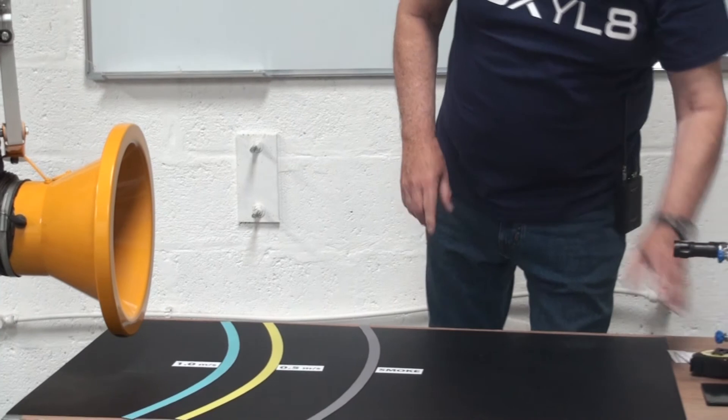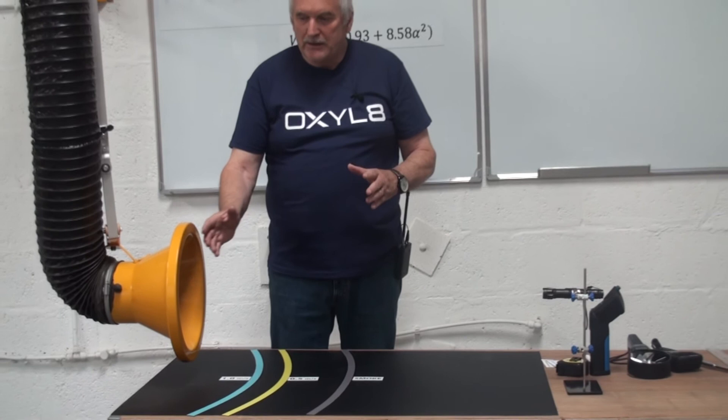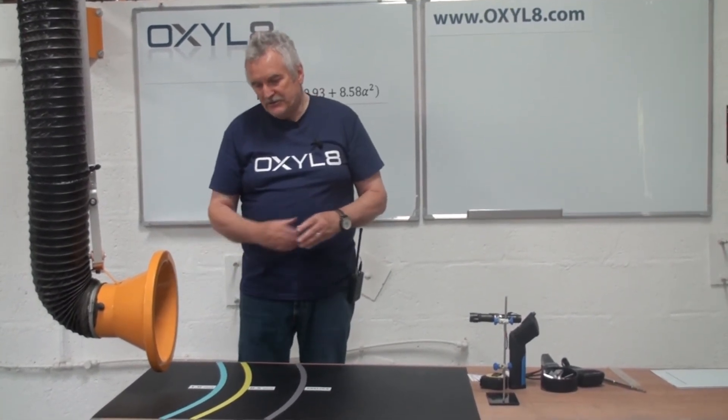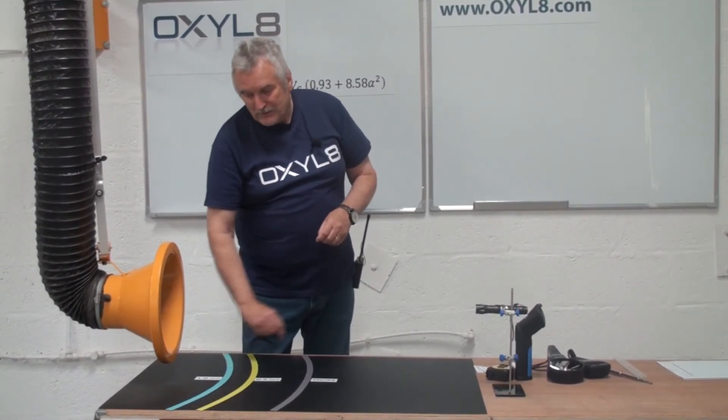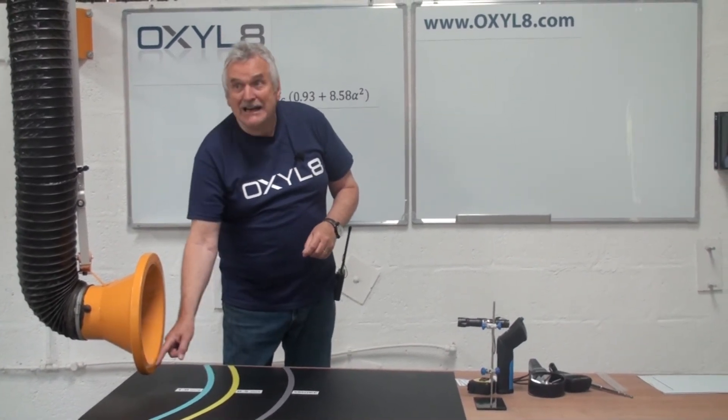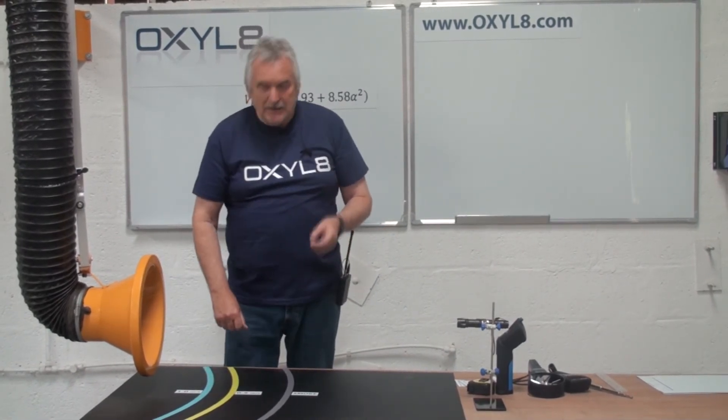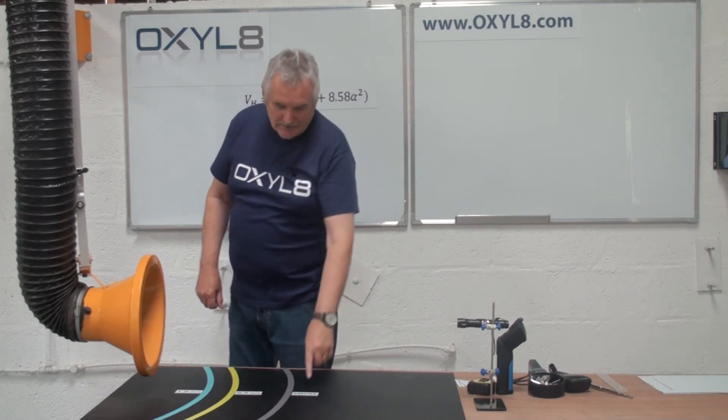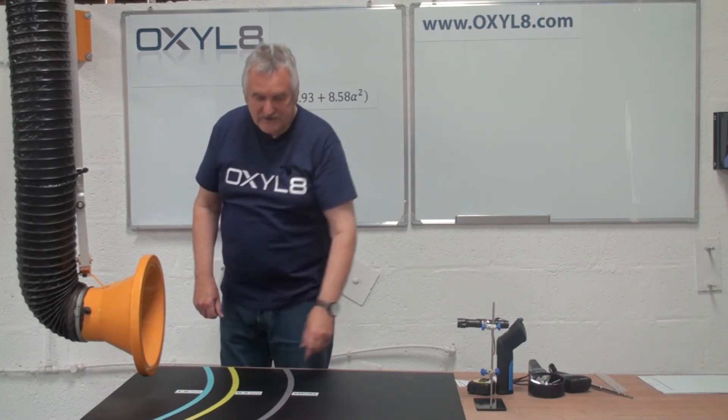That people rarely understand. Number one, it falls enormously as it comes down out from the entrance. You're only going to get 160 mil if you want 1 meter per second from this 9 meters per second hood face velocity. You're only going to get something like 230 millimeters down to 0.5. But if we as examiners, testers, and commissioners rely on smoke only, then it's going to give us a false impression. It's going to show us something like 400 in this case.